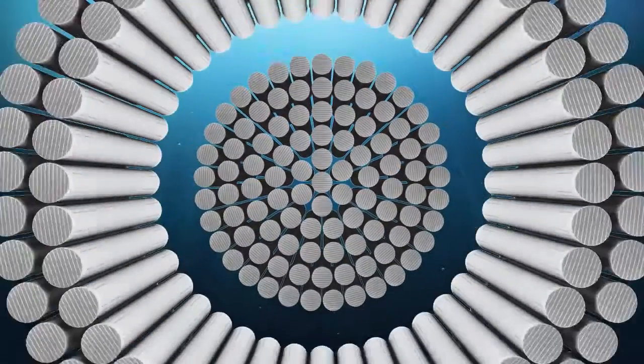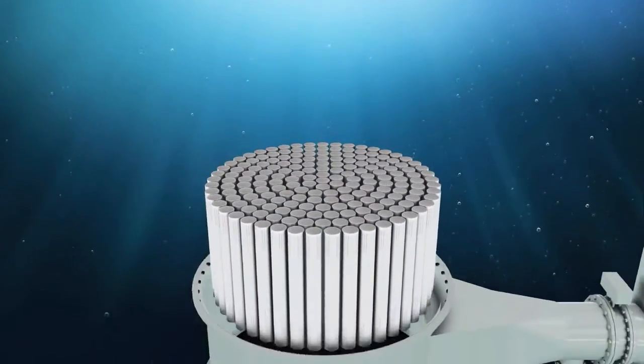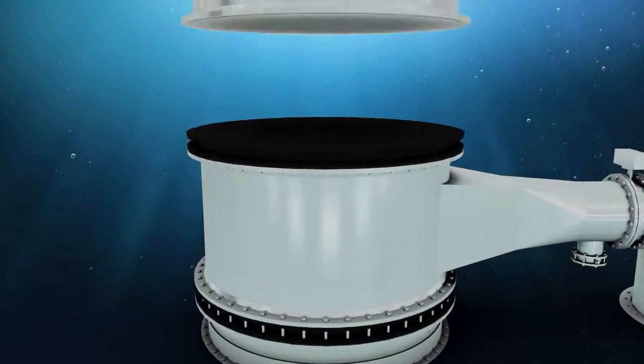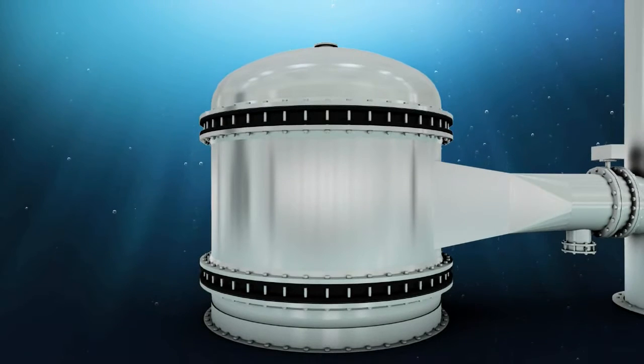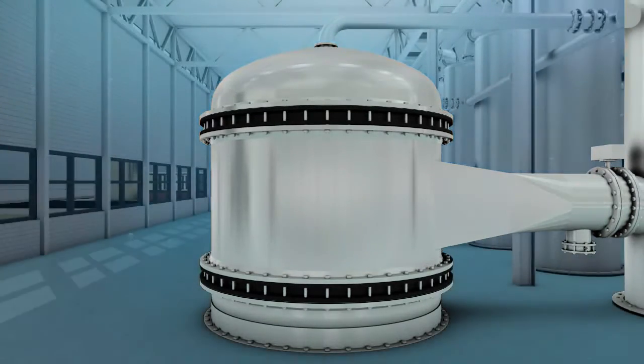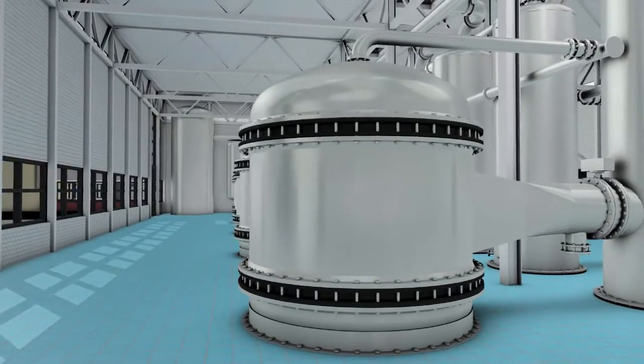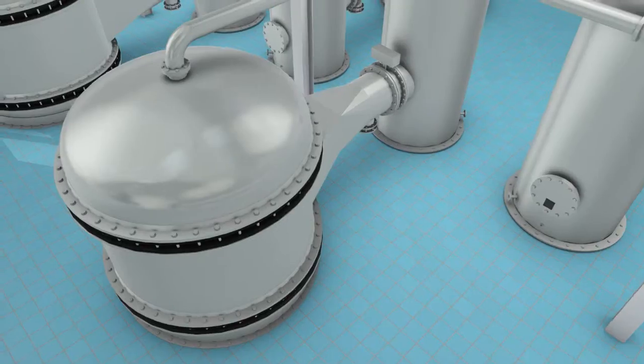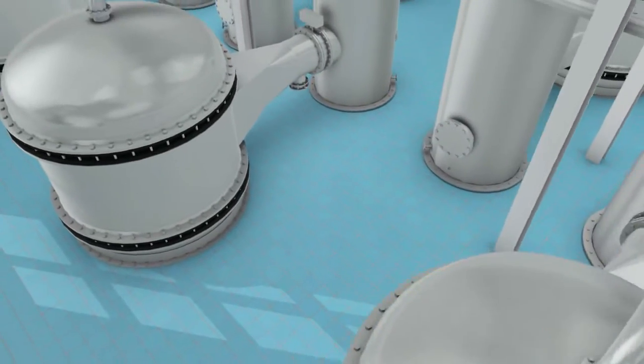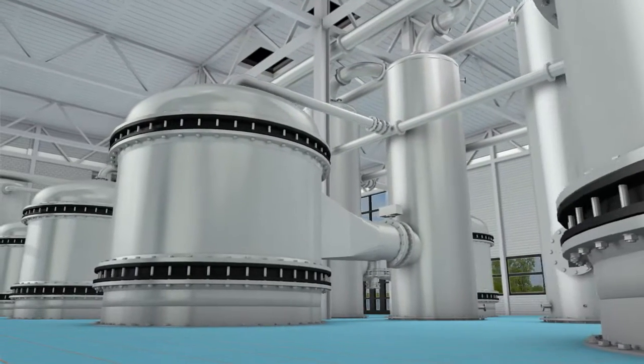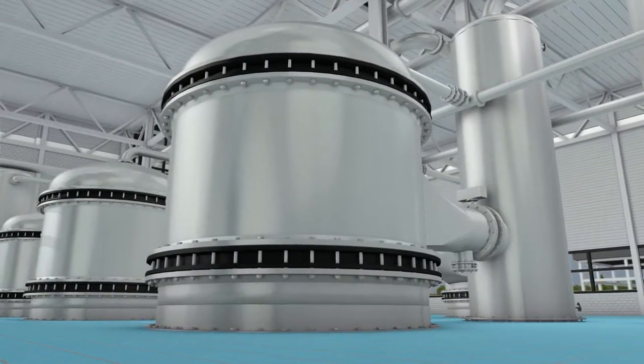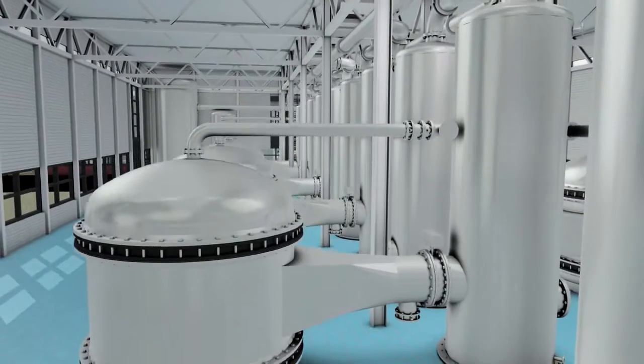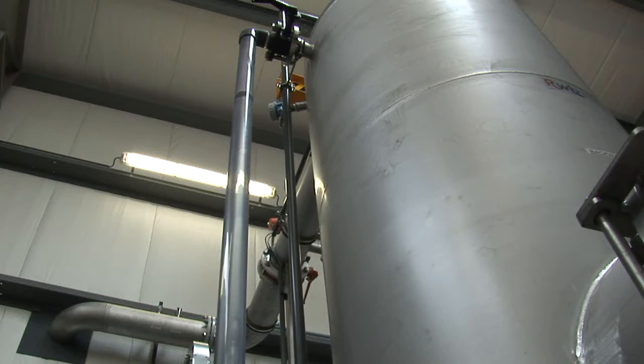Once the water has passed the pores of the membranes, all suspended matter has been removed. The PWN Technologies design of the Ceramac contains 200 ceramic membranes in a single vessel and is the first economically viable ceramic membrane system in the world. Its unique design, with only a few valves, no longer requires separate stainless steel casings for each individual membrane, thus considerably reducing the investment cost. Ceramic membranes can be cleaned with just about any chemical, and their strength allows the use of an incredible backwash pressure of 5 bar.